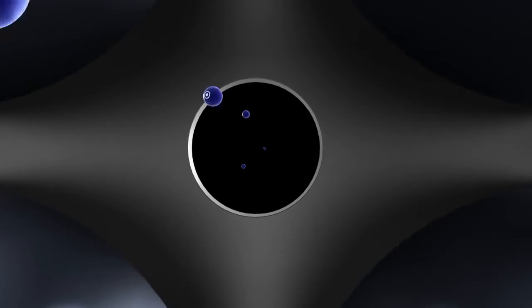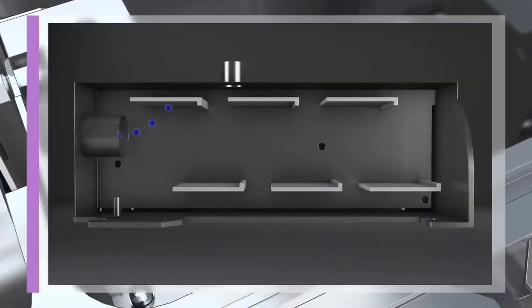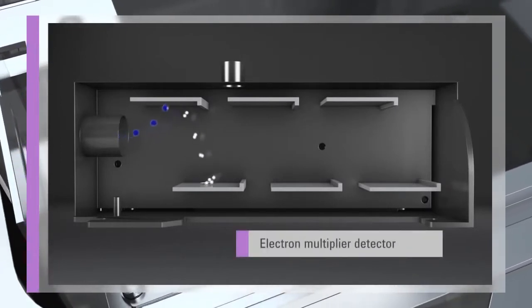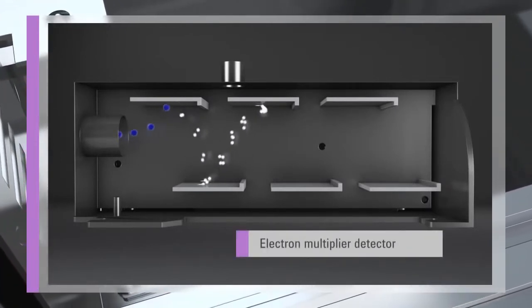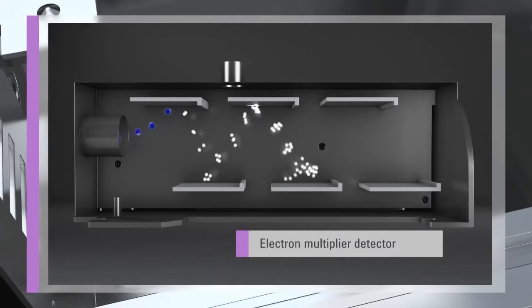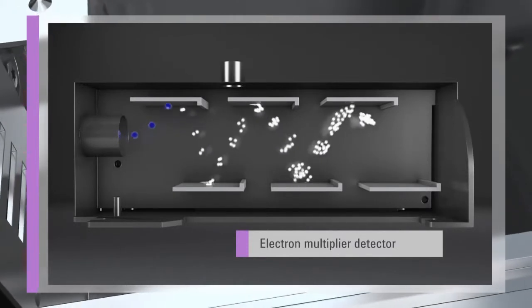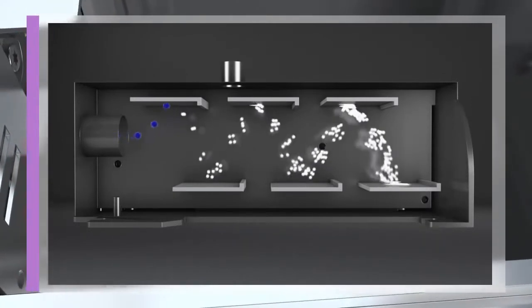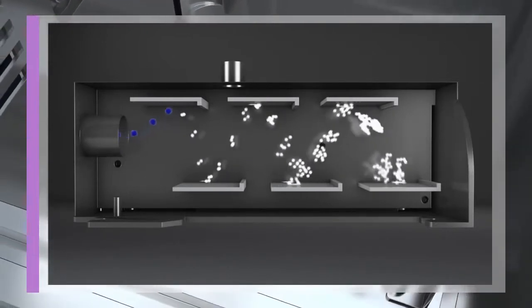The ions selected by the quadrupole are passed to the simultaneous dual-mode electron multiplier detector. The detector covers a full nine orders dynamic range, allowing trace and major elements to be measured in a single run. The 100 microseconds minimum dwell time also makes the 7700 the ultimate system for time-resolved analysis, such as laser ablation or chromatography.